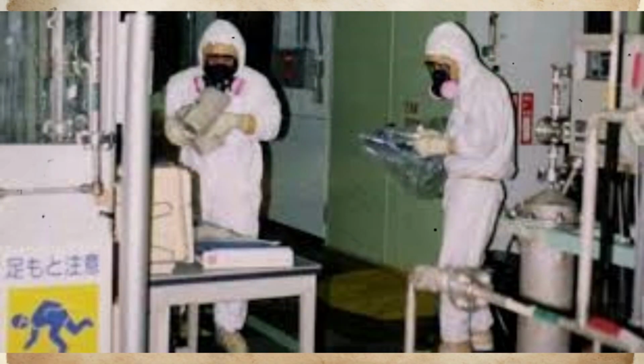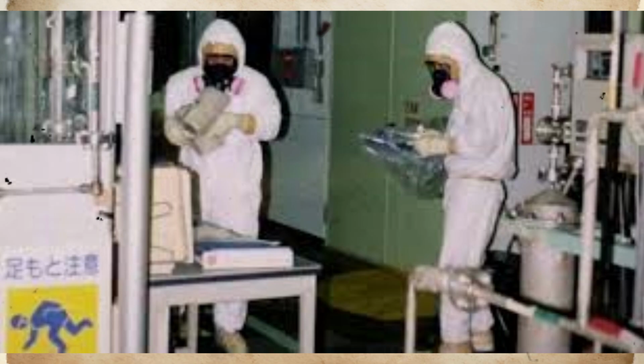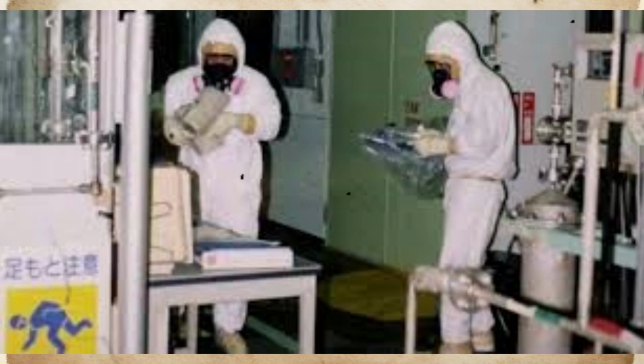The alternative water injection system using fire protection equipment represented the only remaining option for providing core cooling when conventional emergency core cooling systems remained inoperable due to station blackout. Fire protection pumps, designed for much lower pressure operation than reactor systems, could not inject water directly into the reactor vessel while reactor pressure remained at 7 MPa. Reactor depressurization became necessary to enable low-pressure water injection, but depressurization required operating relief valves that depended on electrical power and compressed air systems compromised by station blackout.